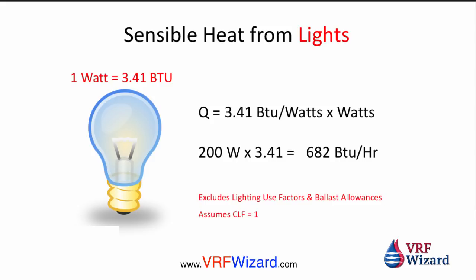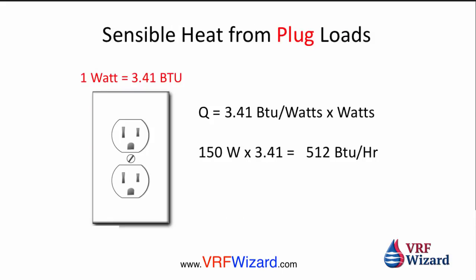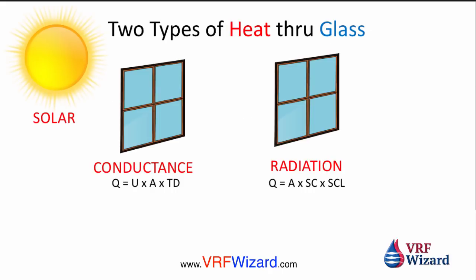For sensible heat from lights, one watt equals 3.41 BTUs. We're not going to figure out usage factors, ballast allowances, and we'll assume the CLF is 1 for now. We just need to know how many watts of lights are burning and convert that into BTUs to size our system and figure out CFM. Similarly for plug loads, we use a straight wattage multiplied by 3.41 BTUs to get the total BTUs.